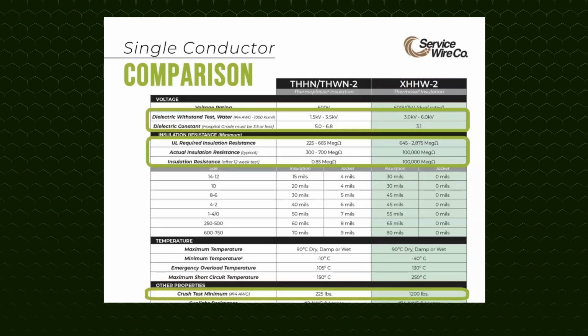In this comparison chart, you can see that ServiceWire's XHHW2 has a dielectric constant of less than 3.5, meaning the cable's insulation has a greater ability to resist leakage current. And the cable's insulation resistance is substantially higher than PVC. This means the cable can handle more spikes and inrushes over longer periods of time while protecting critical circuits at risk of electrical interference from high leakage currents. When it comes to EV charging stations, the cable must be installed underground. This is a perfect fit for our Service Pro X thermoset conductors because the XLPE compound has almost 5 times the crush resistance compared to thermoplastic THHN. Plus, XHHW2 is also moisture resistant.